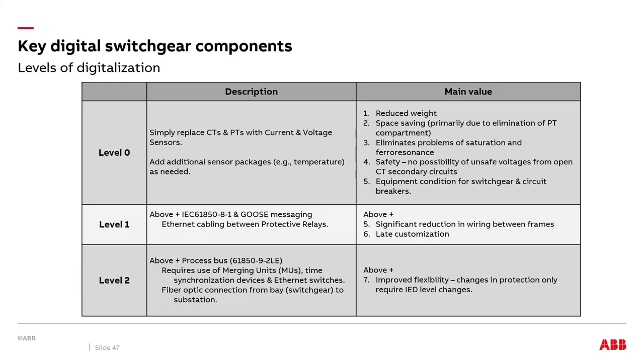What that does is, suppose you want remote control or you want to enable SCADA in your system, you're going to have a relay which is equipped with IEC 61850-8-1, and it's going to talk with the SCADA system. And IEC 61850-8-1 also has GOOSE messaging. GOOSE messaging is basically generic object-oriented substation event, and the operation time is less than 10 milliseconds for distribution systems as per the standards required.